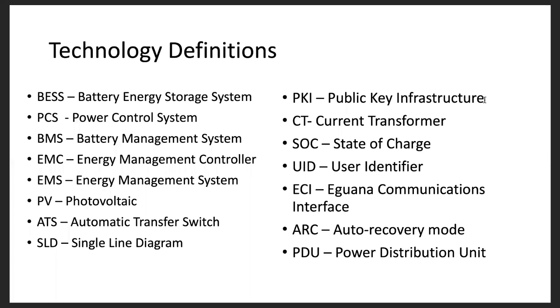For systems where multiple lower SOC thresholds have been exceeded, if the batteries go into sleep or hibernation mode, or even further into a critical low SOC and shut down completely, rather than having to deinstall the battery, ship it off somewhere to have it recovered, or to have any special external charging equipment to recover those battery modules, the system will do an auto recovery of any depleted battery modules. If they can be recovered, it'll use the grid voltage to do that. So it has an auto recovery mode, which is really helpful in cases where it's needed. PDU is just a power distribution unit. It's just a metering function on the EMC.